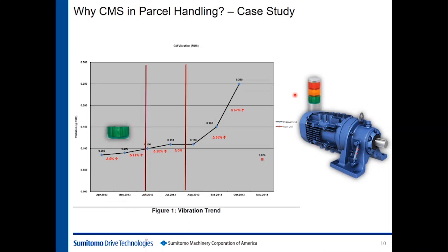So from this data, in the beginning that trend would have been running in the green — everything's normal, been there for a while, then a slight increase. So that tells us something's going on based on the data, and we would probably trigger a yellow light. The yellow light would be an action for an oil change — go check your belt tension, check your slider beds, make sure there's no jams, things of that nature. Then when the data keeps going, that means there's a red. So that tells you right there this is heading towards failure — it's not fixing itself, and they never do. It's time to take advantage of this system and prevent the downtime. So when that red light would have come on in our test, that would have been a three-month period that a person could have scheduled a repair, replaced it on a Saturday when there was no sorting, no operation running, and not lose any production. Then once they replaced it, the vibration on the new reducer went right back down to what a new reducer would have been.